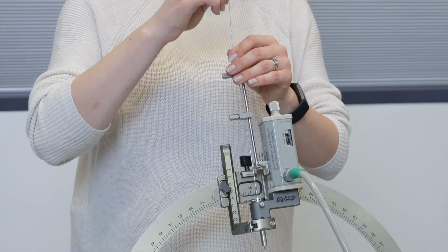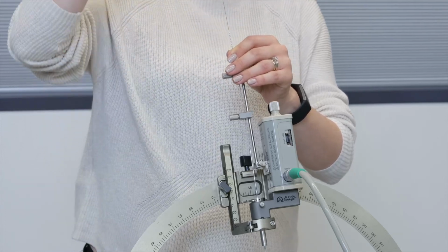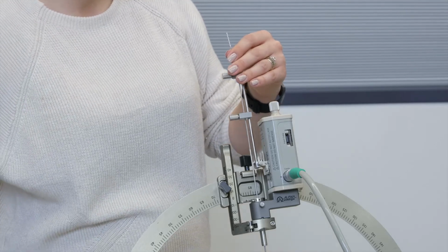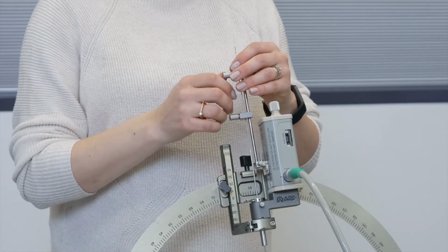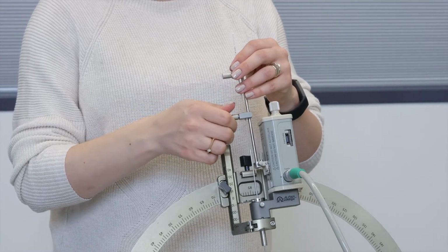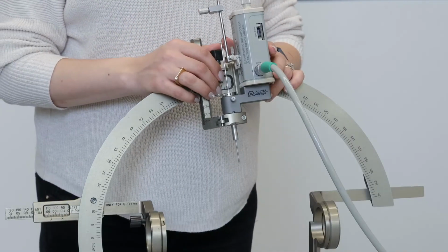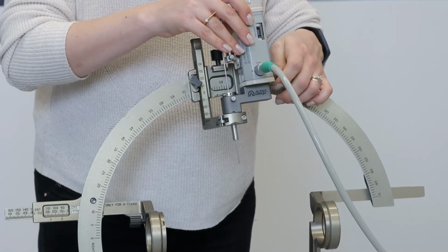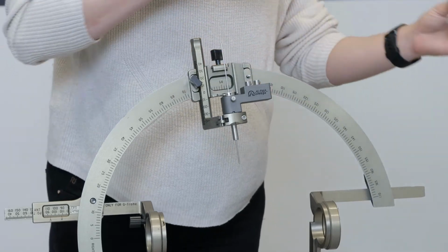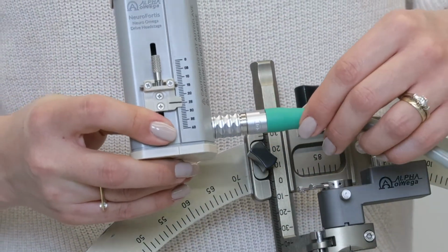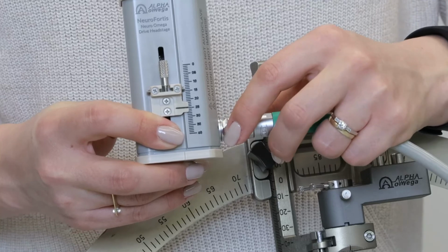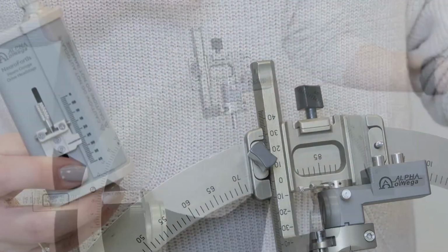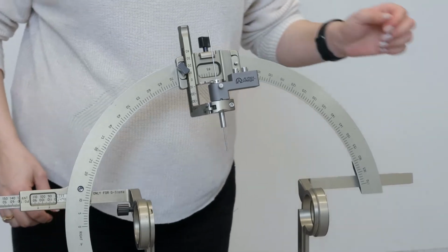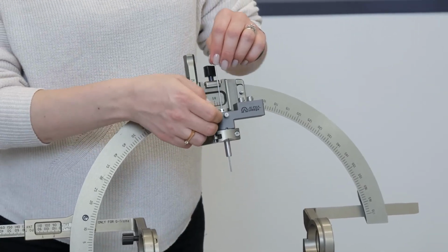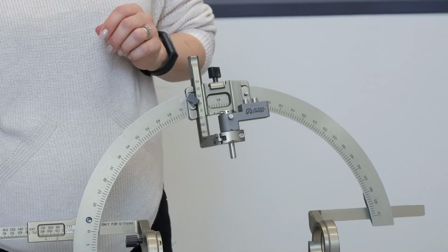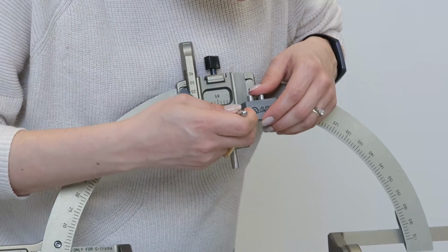Remove the stylet from the DBS lead. Release the DBS lead from the clamps. Once the lead is out, remove the Headstage. Disconnect the Headstage cable from the Headstage. Pull on the connector. And remove the cannula and the frame adapter.